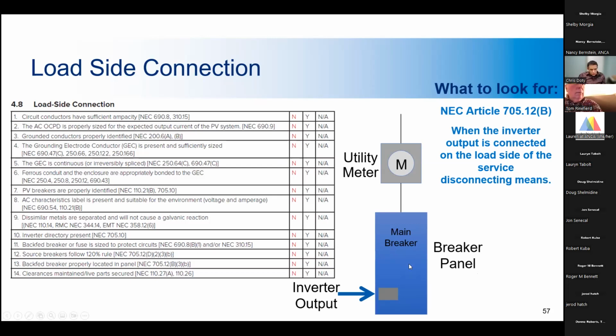And so to determine an acceptable amount of current that can be placed in this backfeed breaker, you would use what's called the 120% rule. So you are able to have the main breaker plus the backfeed breaker, if you can add those up and it is less than 120% of the bus bar rating in the panel, then it's acceptable. And the whole point of this is so that you don't overload the bus bar.